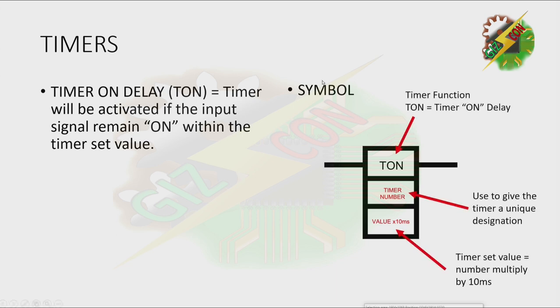Let's go to timers. Timer on delay: the timer will be activated if the input signal remains on within the timer set value. We have the timer function T on, which is equivalent to timer on delay. It is used to give the timer a unique designation — for example, timer 0, timer 1, timer 2, etc. For the timer set value, whatever value you put, multiply it by 10 milliseconds to get the set value.